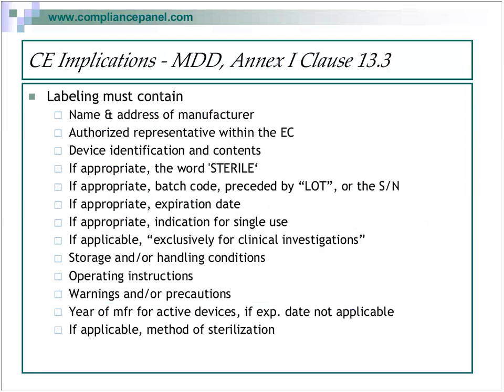Just want to cover, even though the coverage focuses more on FDA, I do want to cover the CE implications for just a minute here. From the medical device perspective, if your device has a CE on it, you're MDD certified, and your labeling has to contain the name and address of your authorized representative within the European community, identification of contents, sterile, lot or serial number, expiration date, indications for single use if that's applicable. If you are using this exclusively for clinical investigations and you want your device to be CE marked, the Medical Device Directive requires that you state that. Storage and handling conditions, operating instructions, warnings and or precautions. You'll have to select which of those is applicable.